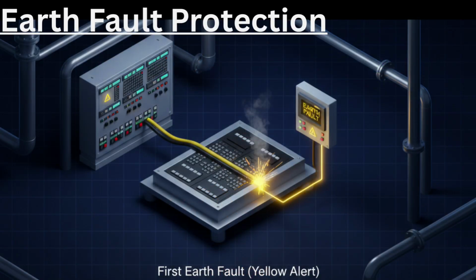Earth fault protection. Earth fault occurs when one phase touches ship body or hull. This usually happens due to insulation breakdown. In marine insulated neutral systems, first earth fault may not trip immediately, but it must be detected quickly. Earth fault monitoring relay gives alarm indication. If second earth fault occurs, serious short circuit may happen. Regular insulation resistance testing prevents earth fault problems. Earth fault protection ensures crew safety and system reliability.